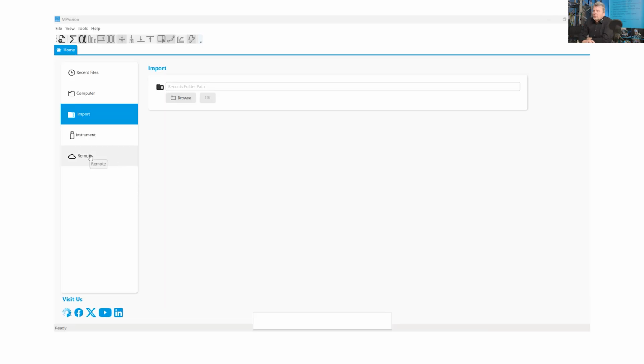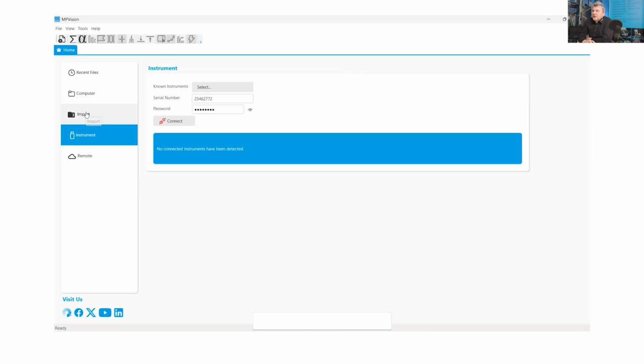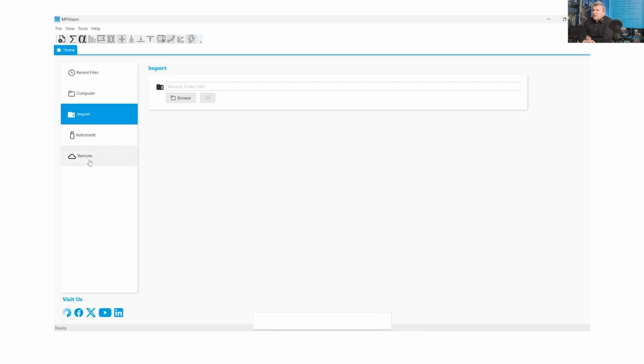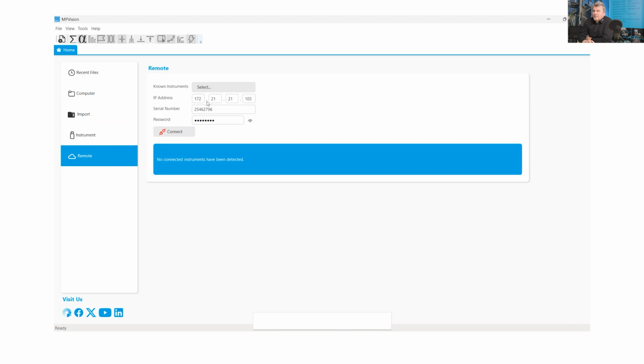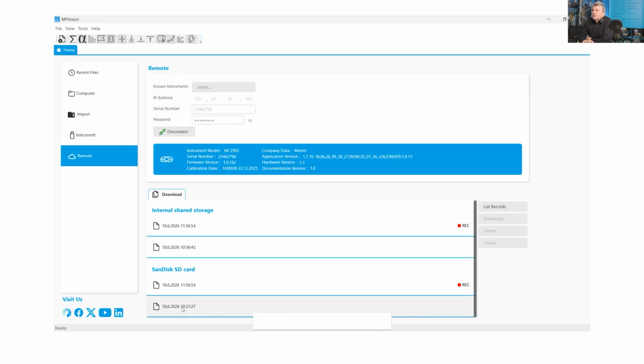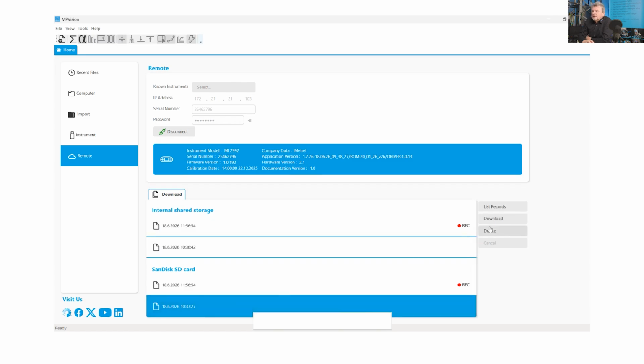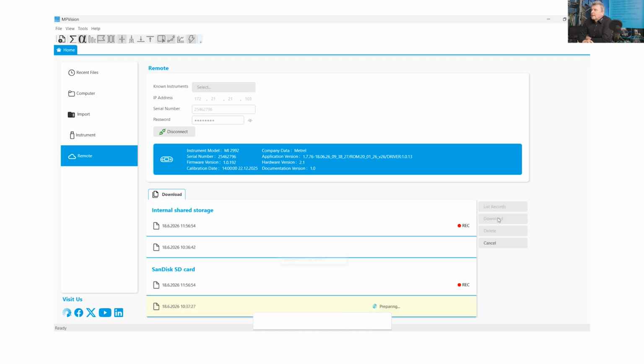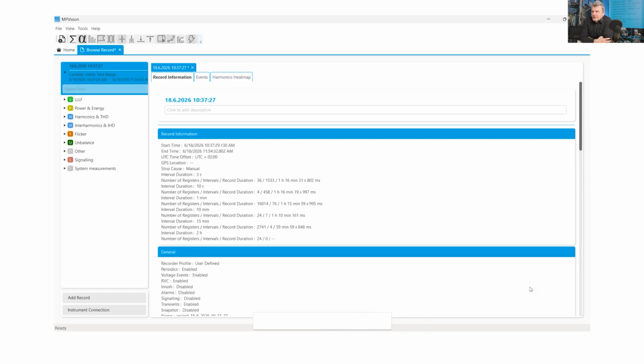So if we check where to download the data, we're offering remote download from the instrument, or directly importing from the file. For a remote instrument, we need to select the IP address of the instrument, serial number, and password. We need to connect it, read the basic data of the instrument, then list the records. We'll read this one, or this one is shorter, and download the data. Comparing the data transfer to the previous one, it is not comparable. It is much, much faster.